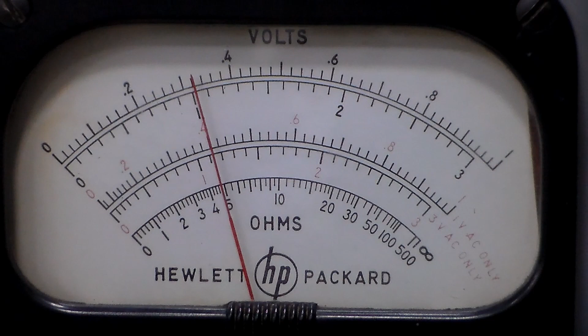I mean, we could go higher. I can go up to 300 volts, and we see the 100 volts on that range is reading quite well, and the Keithley doesn't have capability to go beyond plus or minus 100 volts, but that's fine. After further checks of the AC ranges and the ohms ranges, this HP 410B has just come up and it's within spec and seems to be quite stable, so I'm quite happy with it.